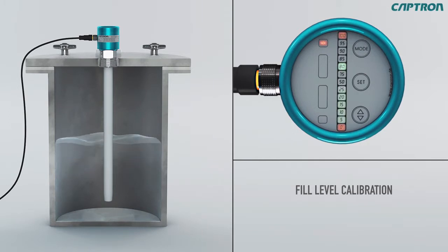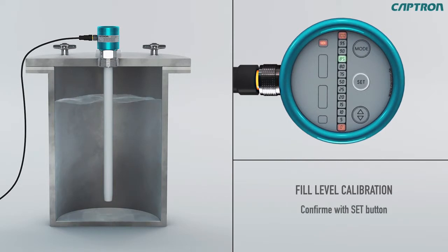Fill the tank now with between 25 and 95% of the desired measurement range. With up-down, you can now set the actual value of the fill level. As soon as you've confirmed the value with the set button, the green display will again stop blinking and the probe will jump after 5 seconds to the next step.